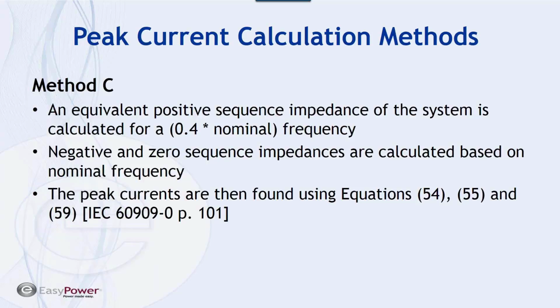But we as engineers know that replacing the frequency in a power system is going to impact the X values, and that's how EasyPower, the IEC, also explains it. So once X gets multiplied by this value, at the end the resulting equivalent impedance gets divided by this value, and if you have only one branch, multiplying and then dividing is equivalent to not even considering this factor at all.